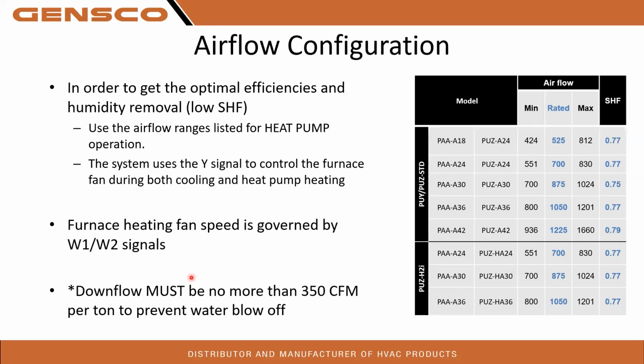Airflow. In order to get optimal efficiencies and humidity removal, we have to make sure the airflow is set up correctly. So here is some of the airflow requirements on the 1-to-1 systems. Please refer to the manual of your coil for airflow requirements on that. It's going to be listed obviously in the manual. Use airflow ranges listed for heat pump operation. The system uses the Y signal on the furnace to control both heating and cooling for the heat pump. It will not be controlling the W1, W2s because that'll turn the gas furnace on. Obviously, we don't want that. So your fan speed settings are going to be based on your Y signal. So when you're changing your dip switches or your pins or whatever you've got, make sure you're changing it on the Y signal.